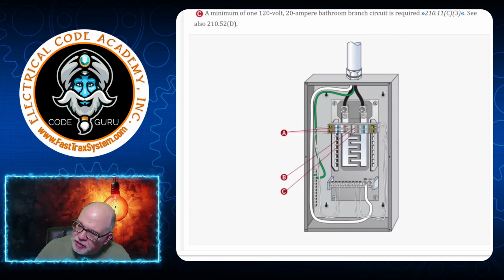Interesting note, this insulated equipment ground is not required to be insulated as shown here in a typical remote distribution panel. It just so happens it is in this illustration. But the funny thing is you wouldn't necessarily need this wire type equipment ground because it looks like the raceway itself is of the metallic type. And that could possibly qualify as an equipment grounding conductor as well under 250.118. Okay, so many things that we can pull from this illustration that you could talk about, have a discussion on, things like that.